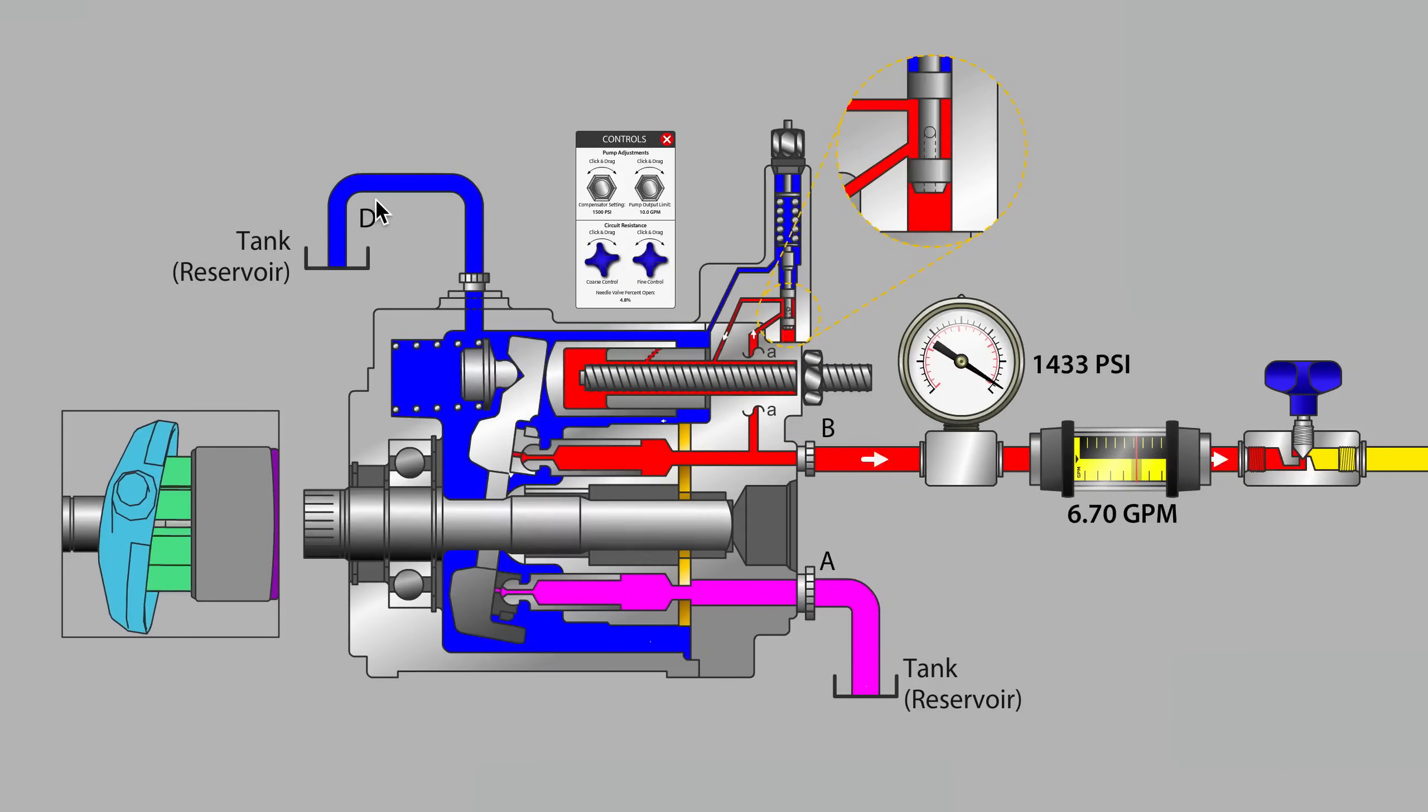As you can imagine, partial blockage on the case drain line will restrict the flow of case drain fluid leaving the pump and complete blockage of the line of course would cause all of the lubricating flows that are occurring inside the pump to stop.